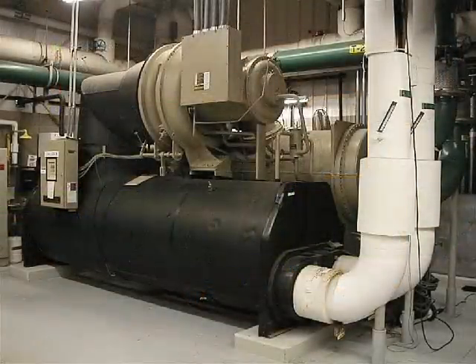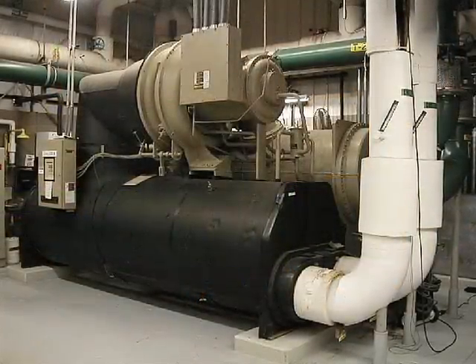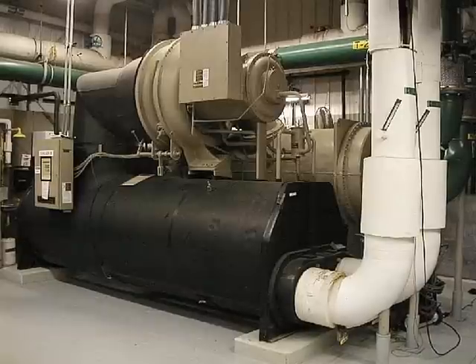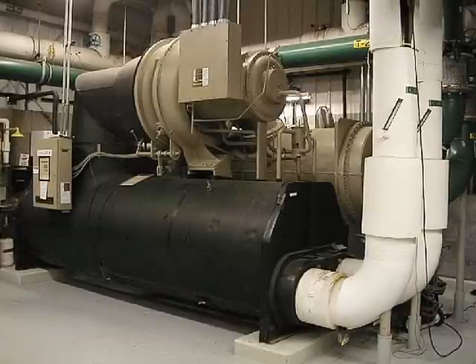Basically, oil finds its way into the evaporator, where it mixes with refrigerant and thus degrades system efficiency and capacity. This occurs when the evaporator tubes become coated with oil, creating a thermal barrier, and the heat transfer efficiency is retarded and drastically reduces the cooling effect.